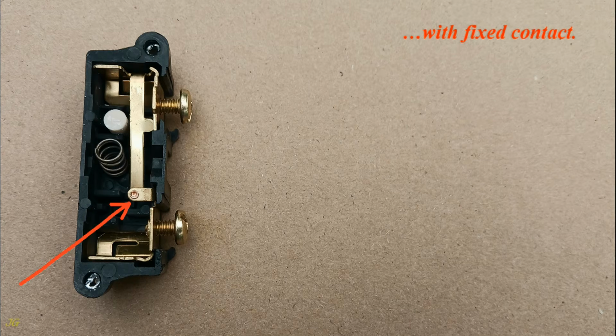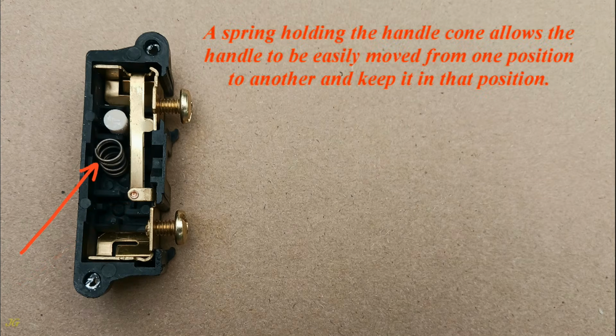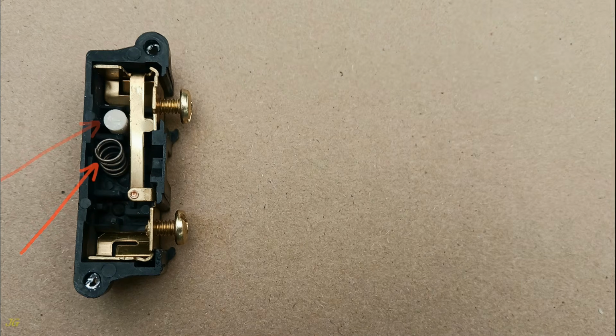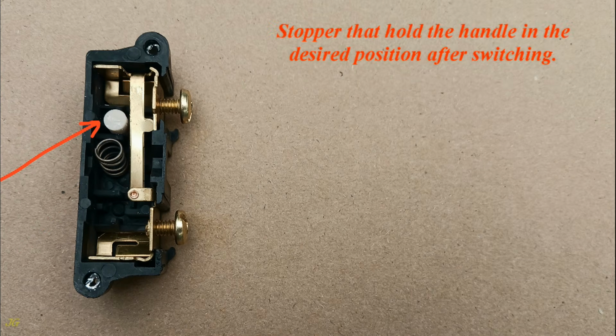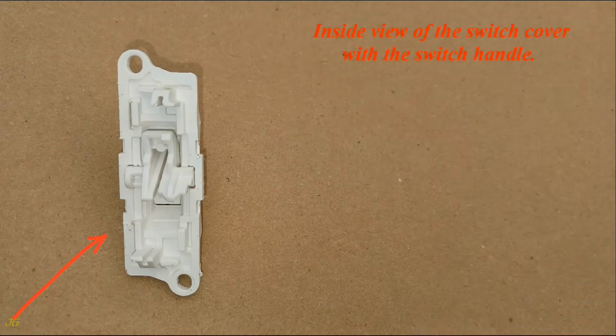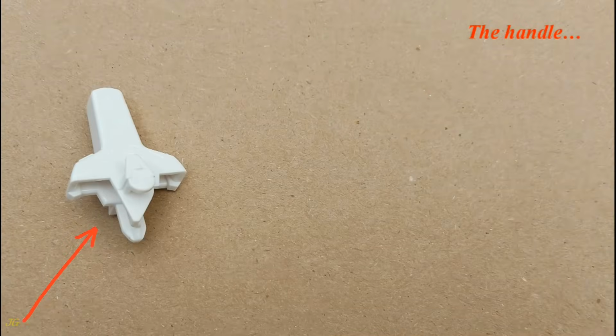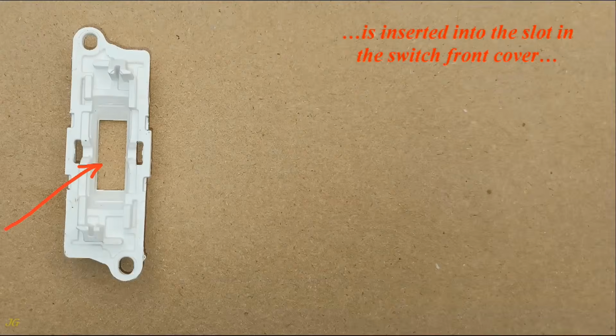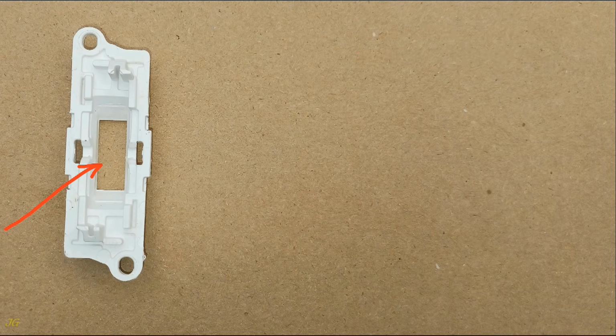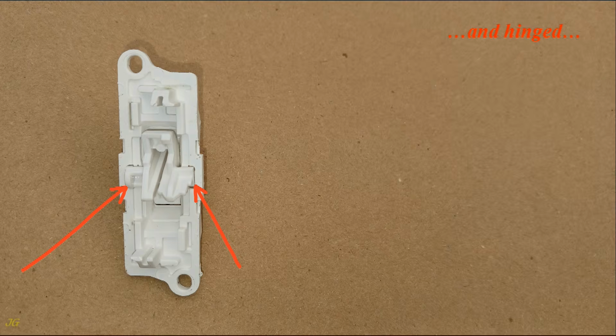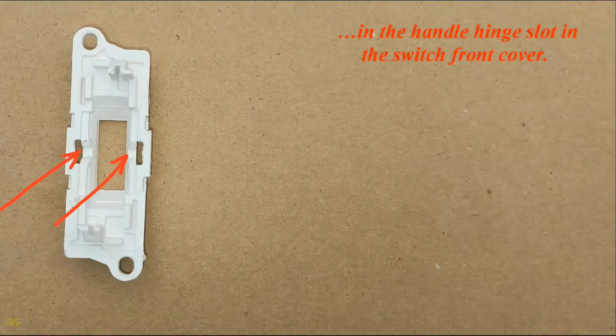with fixed contact. A spring holding the handle cone allows the handle to be easily moved from one position to another and keep it in that position. Stoppers that hold the handle in the desired position after switching. Inside view of the switch cover with the switch handle. The handle is inserted into the slot in the switch front cover and hinged in the handle hinge slot in the switch front cover.